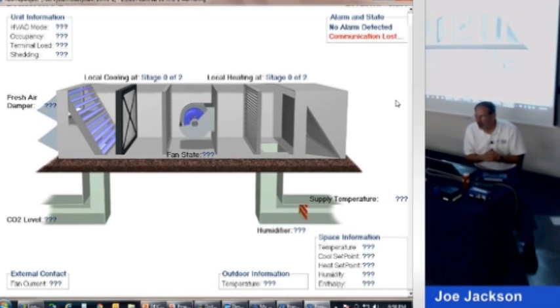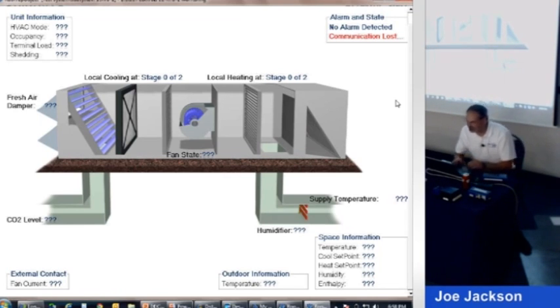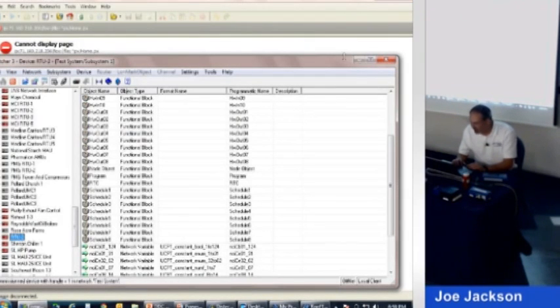Honestly, if I'd known what we were going to do with this and how we were going to use it, and didn't have to talk through it, we could probably set up one of these controllers in less than 1 minute. And a minute later, we have a full-blown graphic of how the unit's operating. We can check all of our sensors and make sure equipment's coming on and off. Configurable controllers are great for that. And the VAV box is very, very similar. The heat pump and fan coils all have the same basic functionality for that piece of equipment.